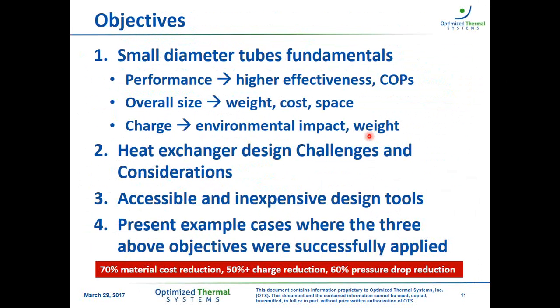So just for you to have a taste of how small diameter tubes can positively impact the performance of these heat exchangers, we have 70% material cost reduction with more than 50% charge reduction and even 60% reduction of pressure drop. So these are some numbers that we found by optimizing heat exchangers for actual real applications.